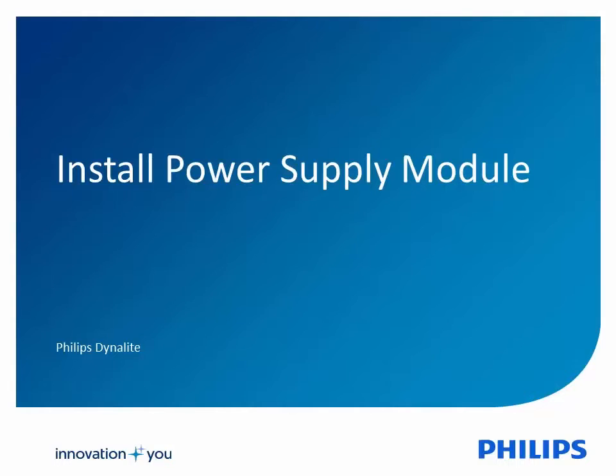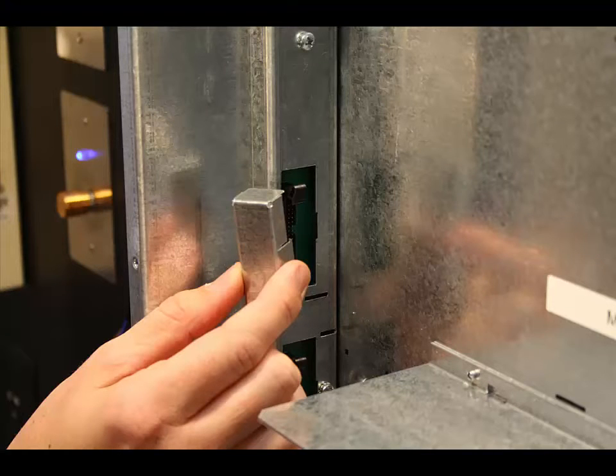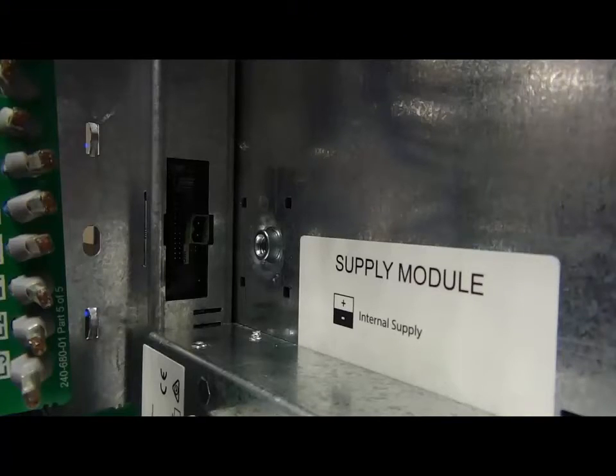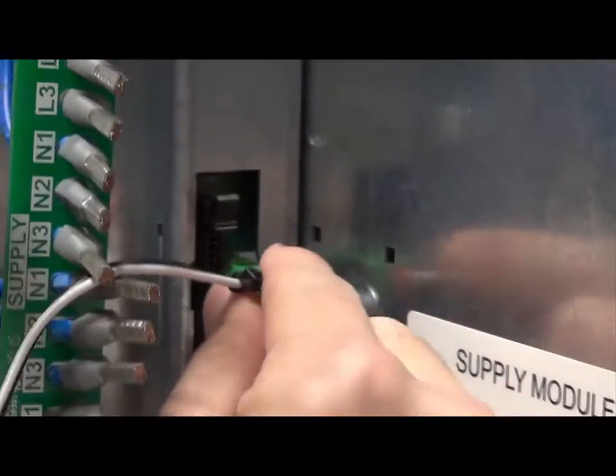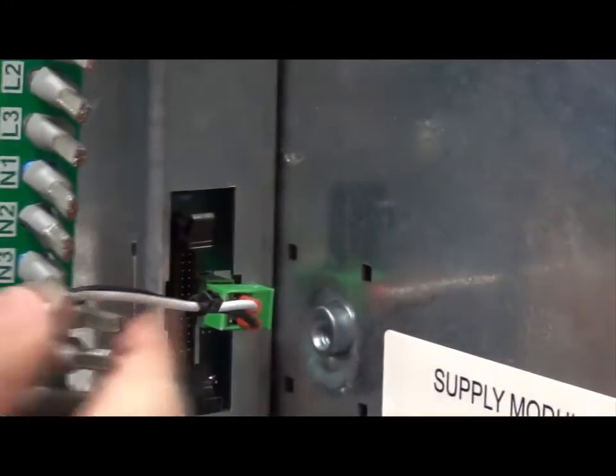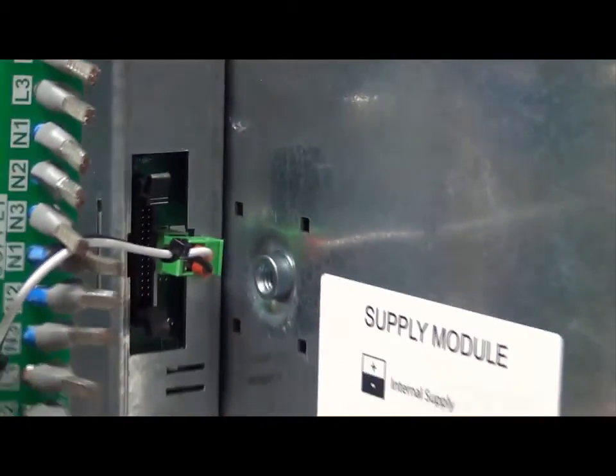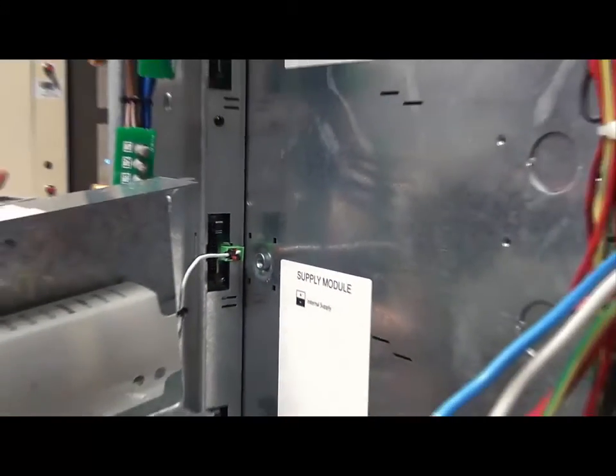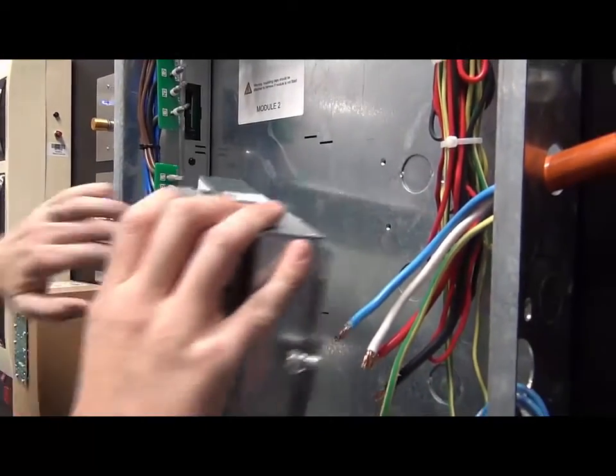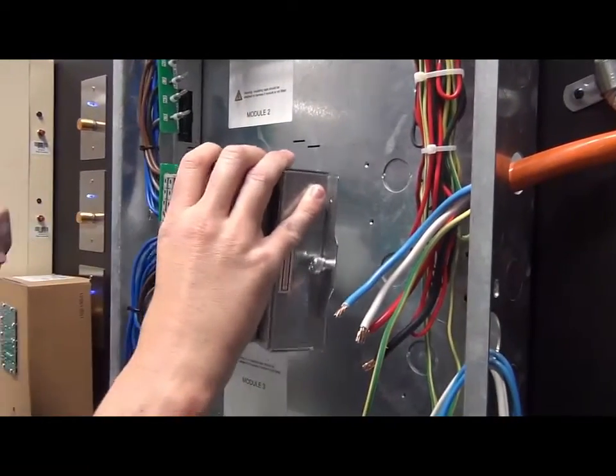Installing the Power Supply Module. The Power Supply Module is mounted in the middle section of the enclosure. Connect the 24VDC Class II SELV supply plug to the two-way socket underneath the DMC communications bus socket. Note that the internal power supply is derived from Phase L1.